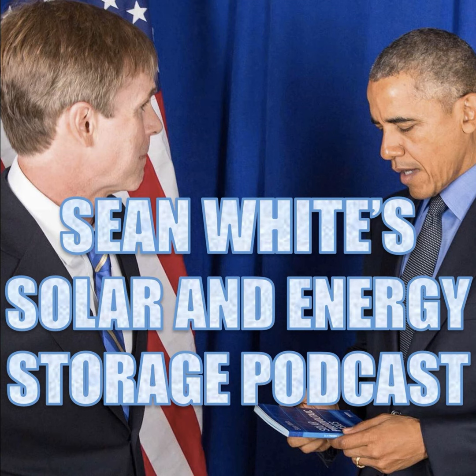Energy management, which is Article 750, was only load management. Everybody's been talking about energy management for decades, right? But nobody ever stopped to ask, well, we're only talking about controlling loads here. We're not talking about controlling power. If you really want to manage your energy, you've got to manage both sides of the equation, right? So you got to do load and source control. And so we finally got that message across, and now load and source control is called energy management.